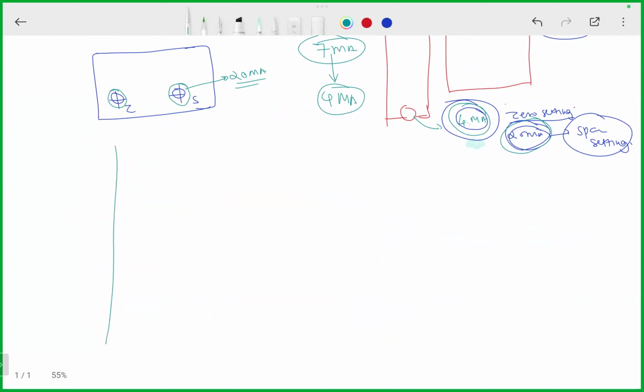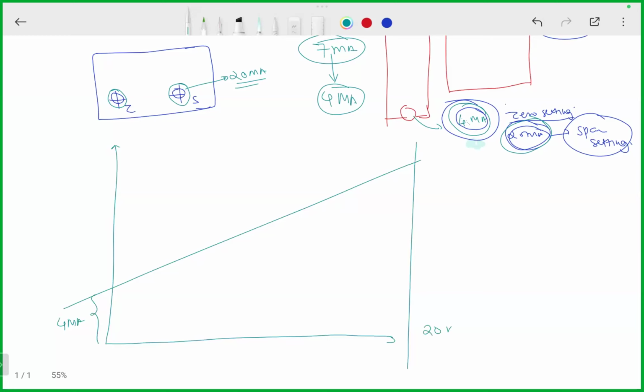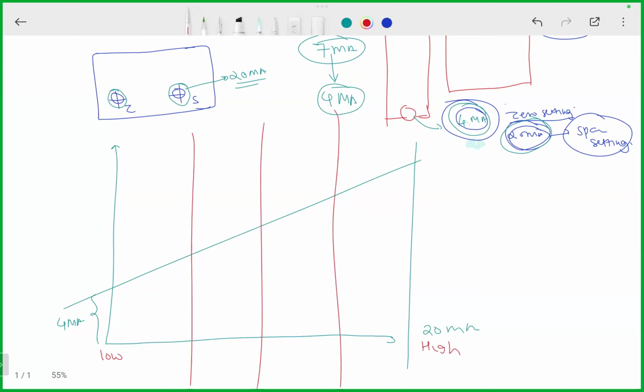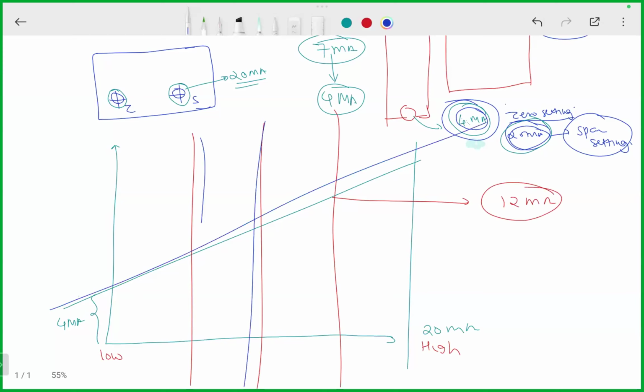Okay. So by doing this, what are you going to get? If I plot a graph, I know that this is my 4 milliamp and this is my 20 milliamp. At 4 milliamp, what is the level? Minimum level. So can I calculate, for example, if my DP transmitter is giving a 12 milliamp signal, what should be the corresponding level? Yes, isn't it? I get this graph. I drew this graph. So I can predict any intermediate position with the help of this particular curve. Is it understood?